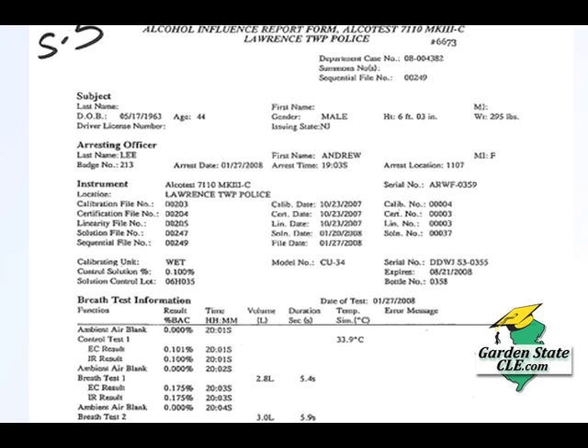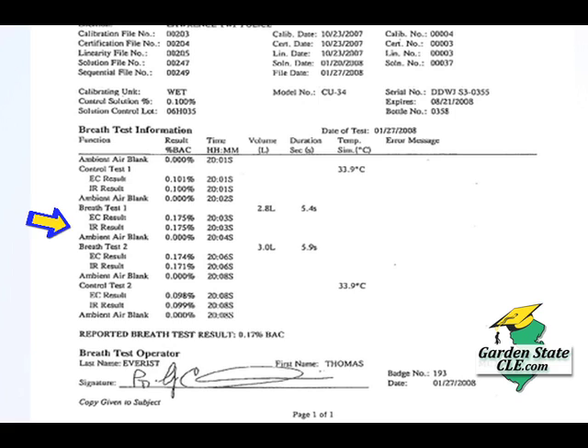This is the AIR. We probably all have seen them. You're going to have the serial number here, the sequential file number, and all of the sequential file numbers for all of those functions performed by the coordinator. Those are listed right above the sequential file number for the AIR. You're going to have a first control test. Should be a 2-minute gap in between each test. Then you're going to have a first breath test. You're going to have 2 readings, right? 2 minutes, a second breath test, 2 minutes, and another control test.